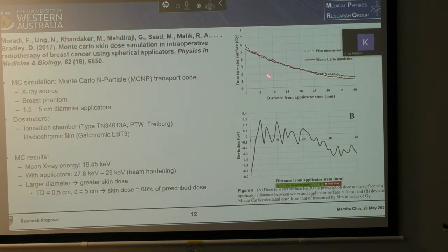This here is a figure of their Monte Carlo simulation in red and their film measurements in black. So this was the dose to water surface as a function of distance from the applicator stem. So as you can see, they agreed fairly well, except potentially at the edges here. And they believe that was due to either uncertainty in positioning the film or due to the response at the film edge. And this here is just the red line minus the black line. So it just shows the difference between the film and the Monte Carlo simulation.